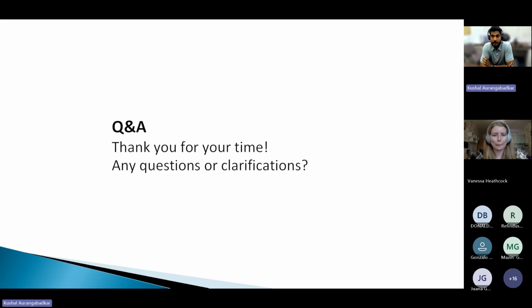I can talk about safeguards. IIAR 2 has a standard for designing a safe ammonia refrigeration system. That's an absolute good document to start with, and it talks about all the safeties and best engineering practices in the industry we need to comply with to design our system and keep it safe and sound. That's a good starting point, and that's what we majorly follow for ammonia refrigeration systems.